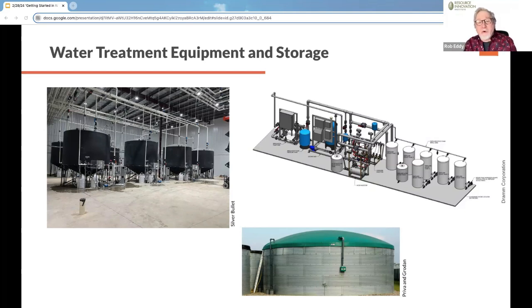You're going to need large doors to get the equipment in, or maybe bring in new equipment or take old equipment out. You definitely want access space around all sides of the equipment of at least 3 feet, so you can go after leaks and repairs and just make it ergonomic for your technicians to work there. Lastly, water should never be left stagnant in tanks, even if it's cleaned up. You need to have it circulated constantly through a disinfection loop, such as a UV light.